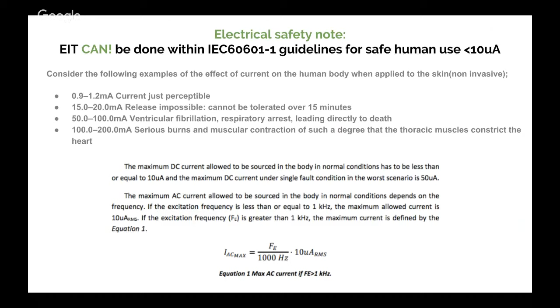If you're wondering whether sending a little AC current through your body is safe, it is, as long as it's within the guidelines for safe use on humans, which is less than 10 microamps. And that's a set of standards called the IEC 60601-1 guidelines. So just to put it in perspective, you know those electrical ab stimulators that they advertise on late night TV? They're a few milliamps. So this is less than 10 microamps. So very tiny current is applied, absolutely within the safety standards.